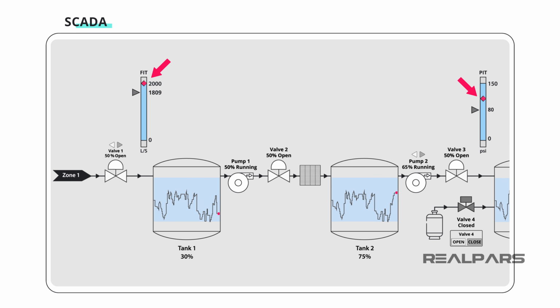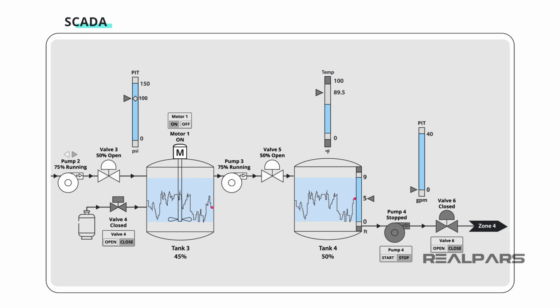Process set points would also be located on a screen. These set points may be used to modulate valves to maintain flows or pressures, start, stop, or vary the speed of motors, select which equipment to run, or how many pieces of equipment to run to produce the desired quantity of water. The set points might also be used to indicate alarming when a process reading is outside of some defined limit.